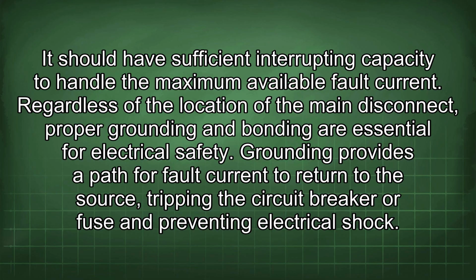Regardless of the location of the main disconnect, proper grounding and bonding are essential for electrical safety. Grounding provides a path for fault current to return to the source, tripping the circuit breaker or fuse and preventing electrical shock.